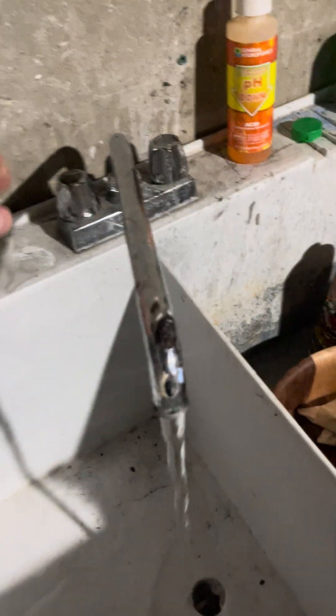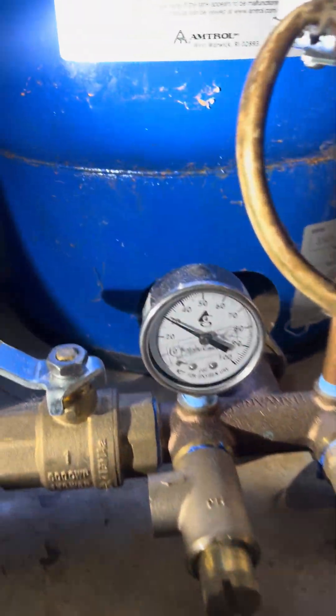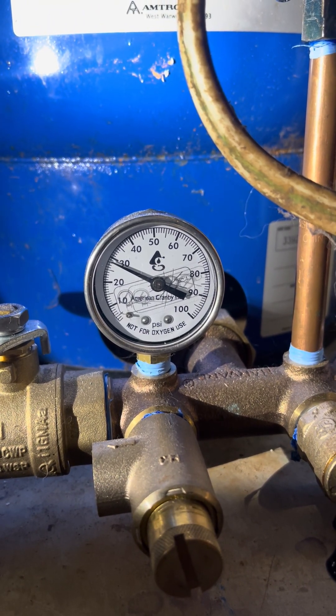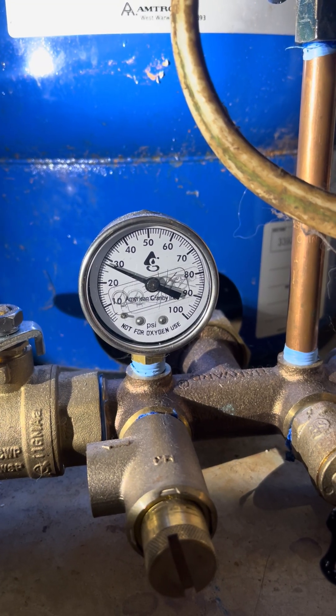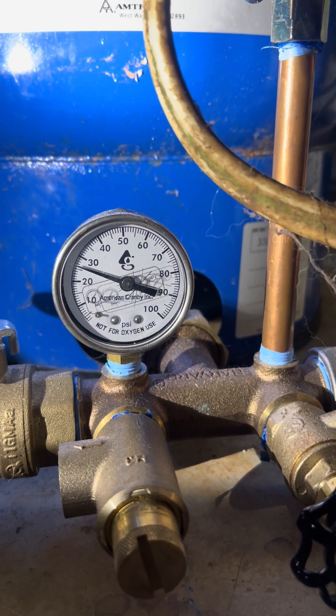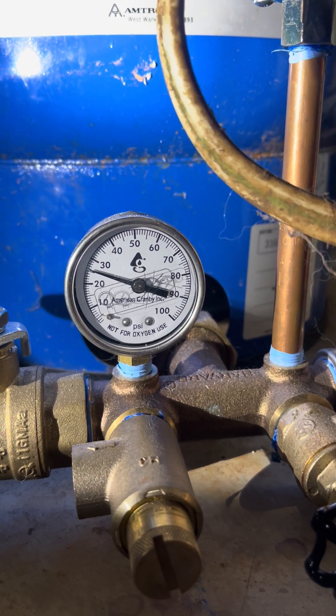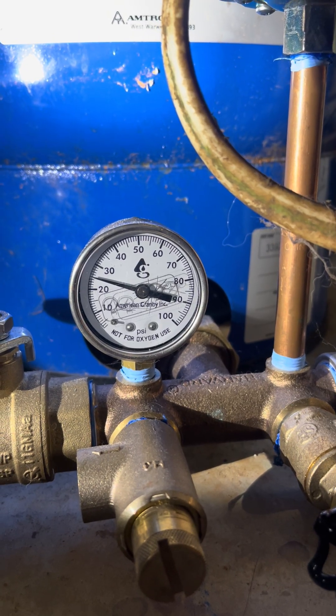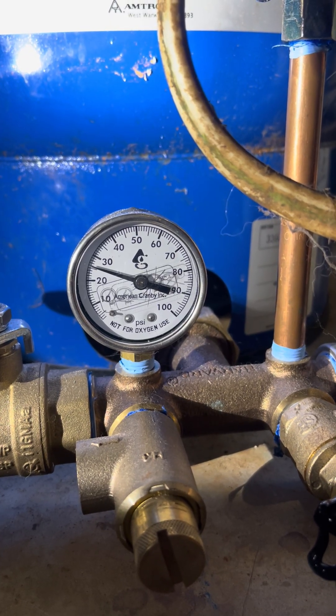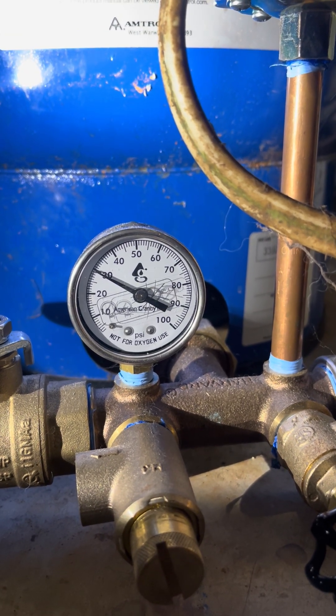Come over here — we're going to kick on our water. The well pump gets kicked on. We're going to go watch our meter. You can see it's losing pressure, going down. So we still need to increase this a bit more. It just kicked on at about 24 psi, so we're halfway there.